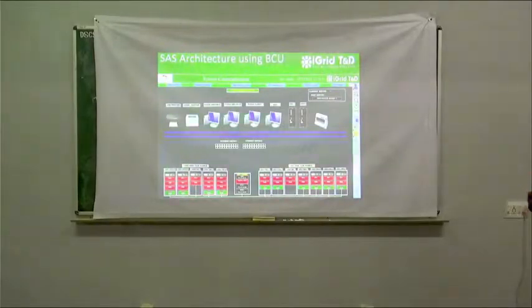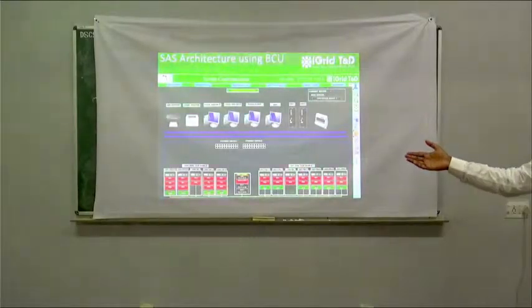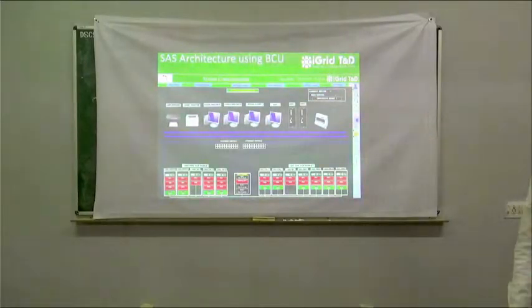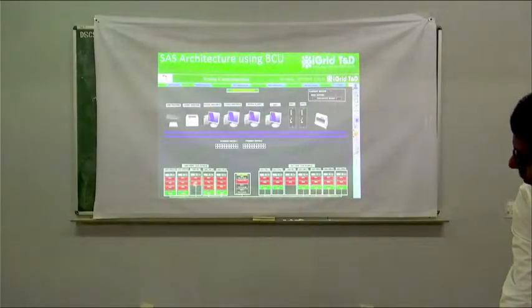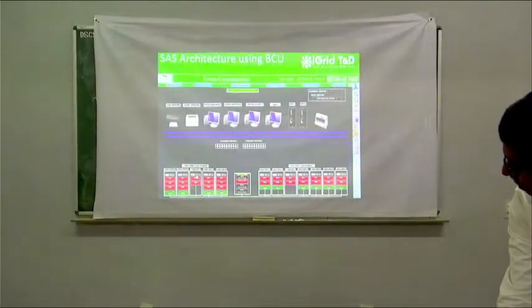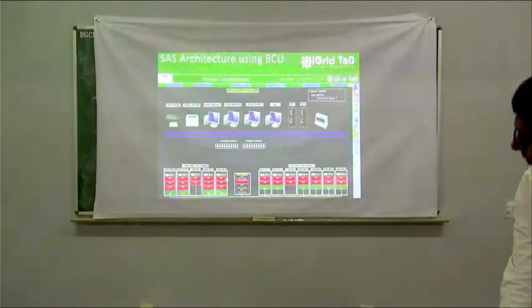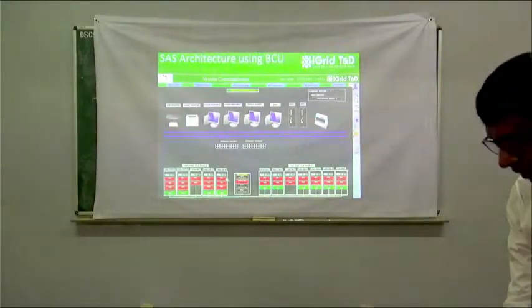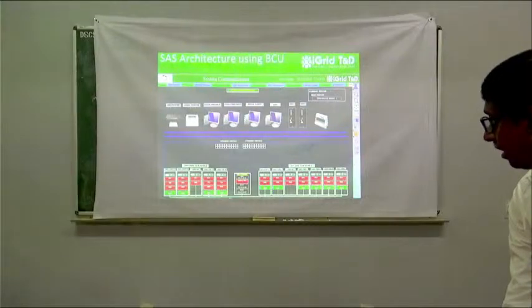Now all these relays have got an IP address. What we do is set up an IP address for all these devices, and they are connected in the network to an Ethernet switch. Based on the requirement, for example, we have two feeders, one bus coupler panel, and one transformer panel. Now all these things are finally connected to the Ethernet switch which is there in the SAS panel.